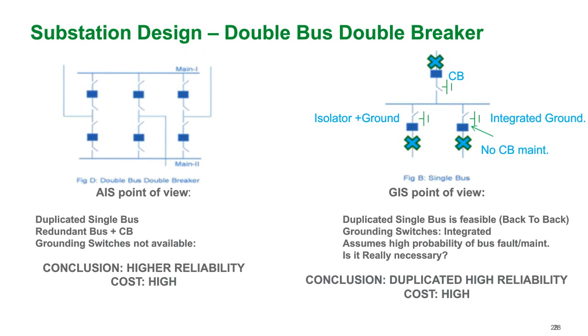Now again, a double bus with a double breaker. This is a similar kind of design concept to transfer bus, but in this case, you have redundancy of your circuit breaker. So you potentially have protection of your alternate bus here. So you have an even higher reliability of your air insulated switchgear, but the cost is extremely high for this because you have completely redundant bus and completely redundant circuit breakers. So you can double, or if not more, increase the cost of the switchgear lineup.